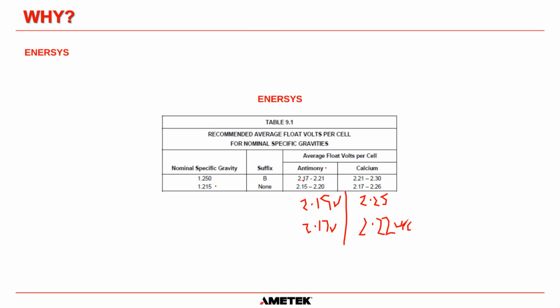volts per cell. And then if you had 60 cells in the string, you would multiply any of those values by 60 to get your float voltage. So 60 times 2.25 is the common 135 that we say, but you can see for this high specific gravity antimony cell, it would be 60 times 2.19, which would be just short of 130 volts. Actually, no, let me do the calculation. It's not short of 130 volts. That's what iPhones are for. Everybody's shouting at me down the screen.